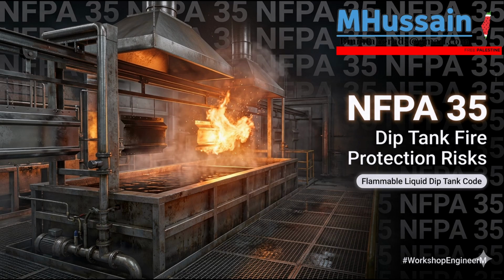It's a terrifying scenario. Imagine the burner under a massive kettle is firing normally, but a draft, or a fuel hiccup, extinguishes the actual flame, yet the gas valve remains open. Oh no! You're now pumping massive volumes of unburned natural gas into an incredibly hot, enclosed firebox. The moment that gas cloud finds a hot enough surface or an ignition source, the resulting explosion will destroy the furnace and potentially rupture the entire kettle above it.